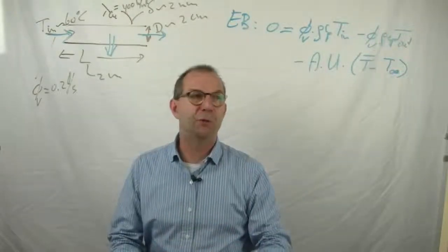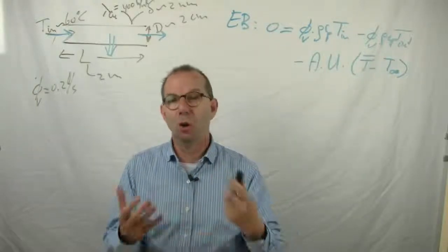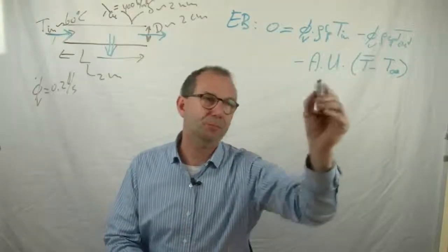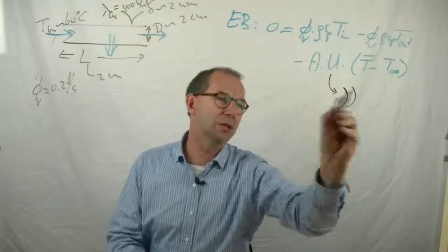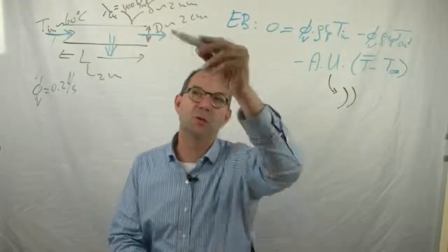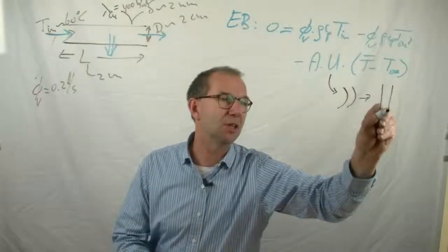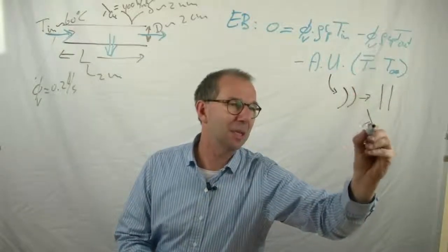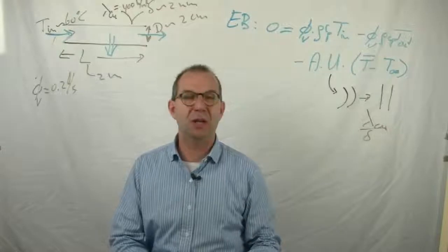Now I'm going to assume first that there is no external heat resistance. All heat resistance comes from the copper. That's a worst case. And then I deal with, okay, this is a kind of a curved wall, heat is going through it, but the wall is relatively thin compared to the curvature, to the diameter of the tube. So for a first estimate I can do as if this is a thin flat plate. And thus U is then estimated as lambda of copper over the thickness delta, the thickness of the wall.